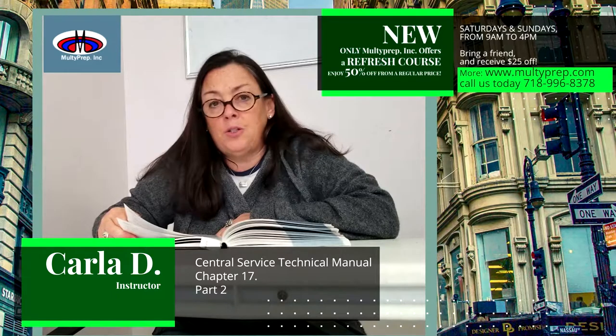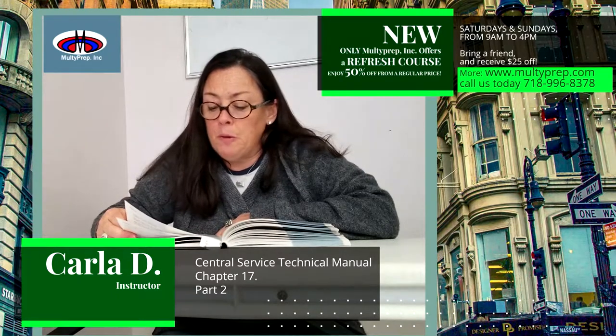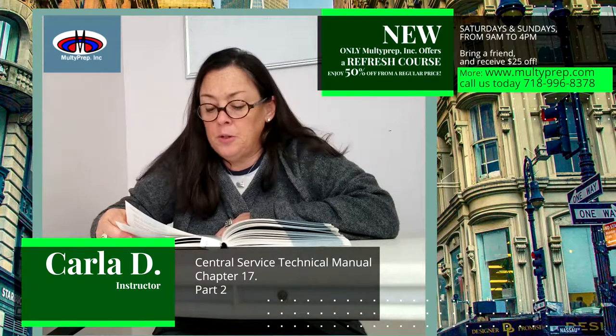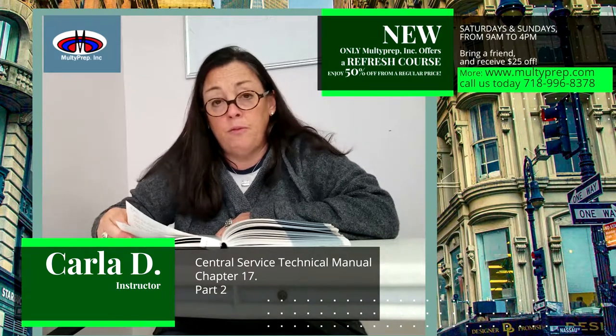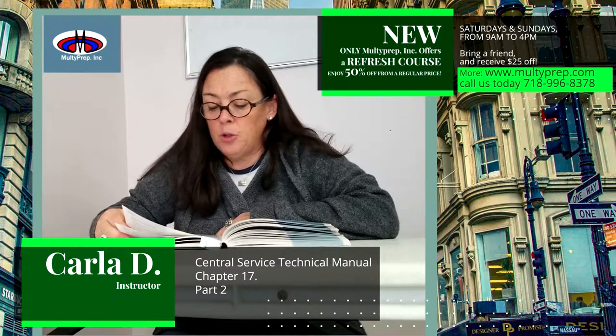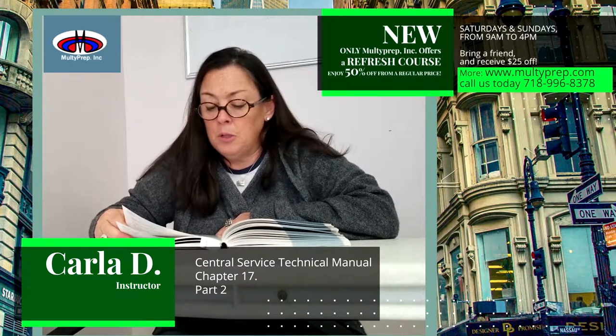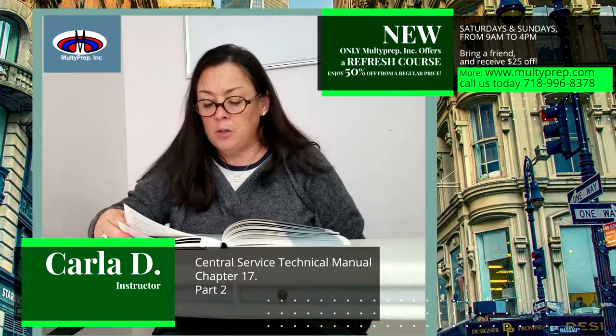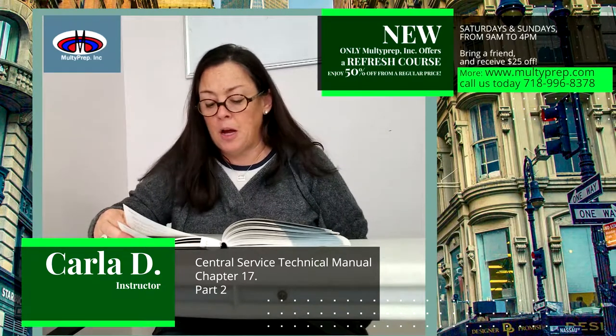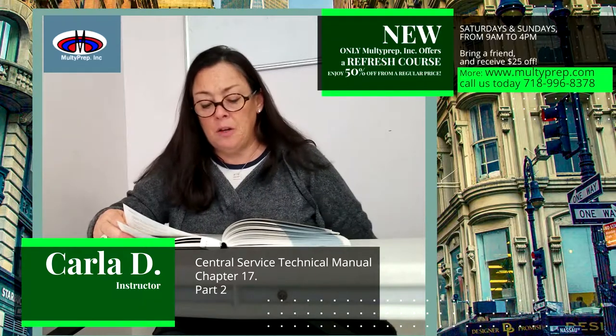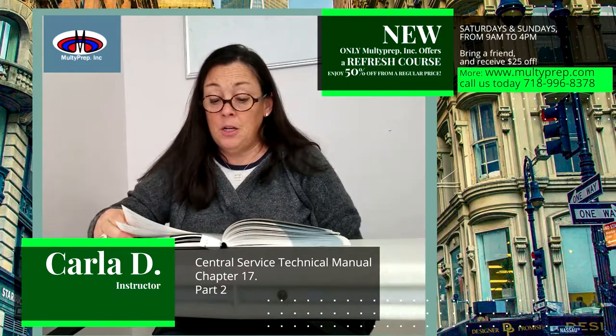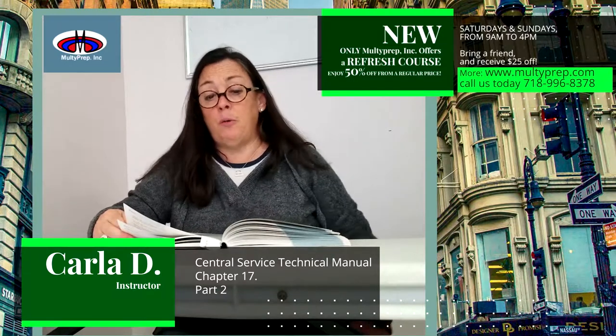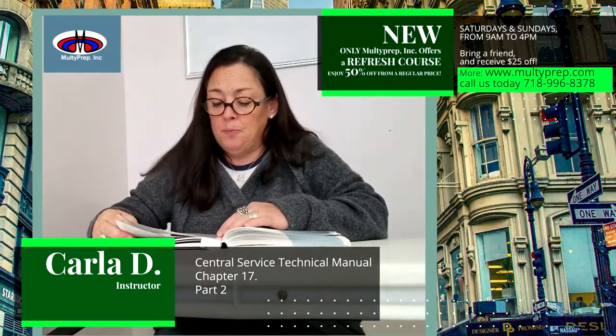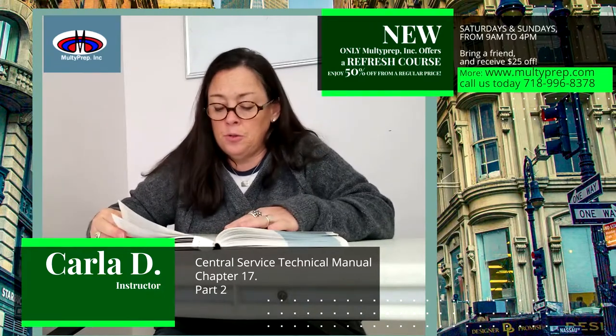Biological indicators and process challenge devices. The spore-producing microorganism used in gravity steam sterilizer testing is Geobacillus stearothermophilus. It is recommended that commercially prepared PCDs be used. The materials utilized in the packages remain consistent because they are manufactured for single use. So there is no wear or erosion of the product. Again, if commercially prepared packs cannot be used, refer to ANSI AAMI ST79-2013, section 10.7.2.1. Ensure that the PCD to be used is designed for gravity sterilizers.